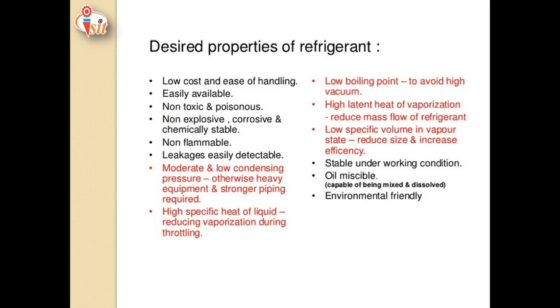The refrigerant should have a low specific volume in vapor state, thereby reducing equipment size and increasing efficiency. It should be stable under working conditions. Oil miscibility — the capability of the oil used to mix and dissolve with the refrigerant — must be checked. Most importantly, the refrigerant must be environmentally friendly. For example, CFCs (chlorofluorocarbons) were used as refrigerants in earlier days but damaged the ozone layer, so such refrigerants should be avoided.